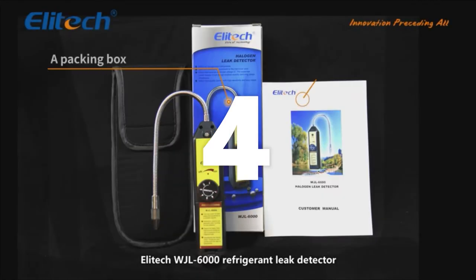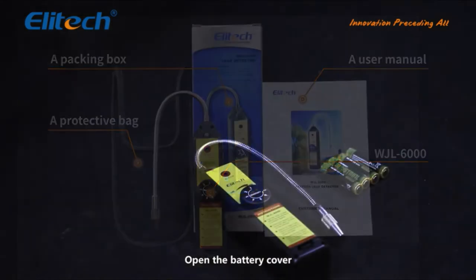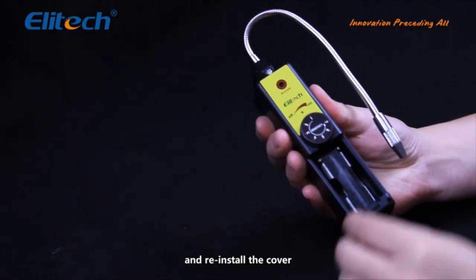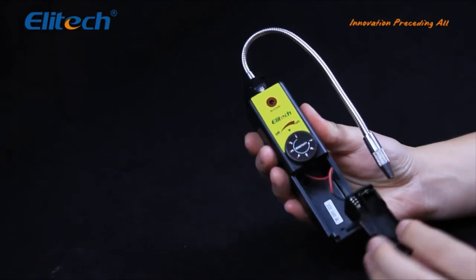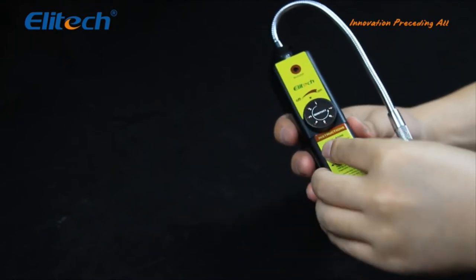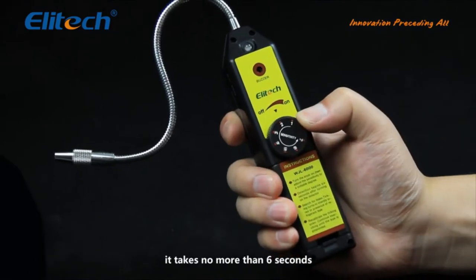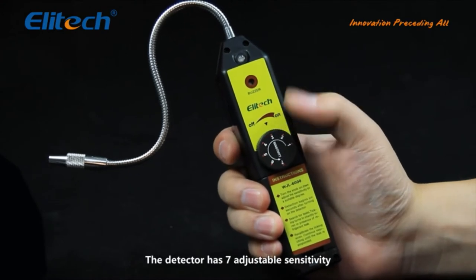The Elitech WJL-6000 refrigerant leak detector adopts a corona refrigerant sensor. Open the battery cover, install four triple-A alkaline batteries, and reinstall the cover. Turn on the detector — it takes no more than six seconds to warm up until it beeps.